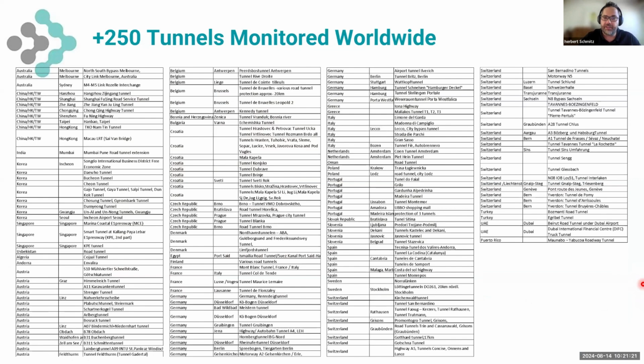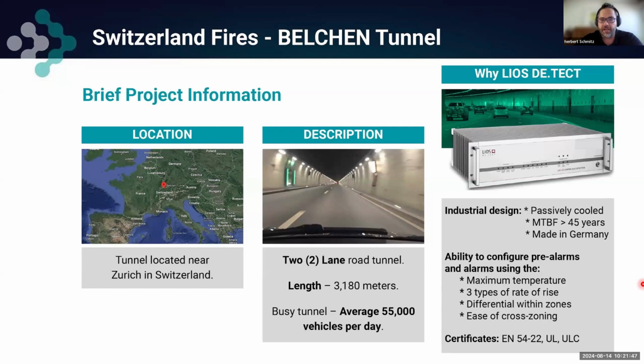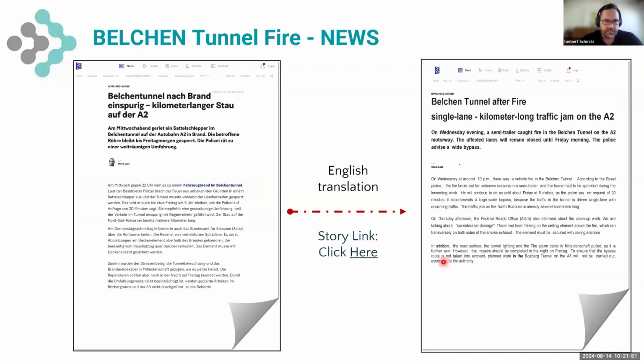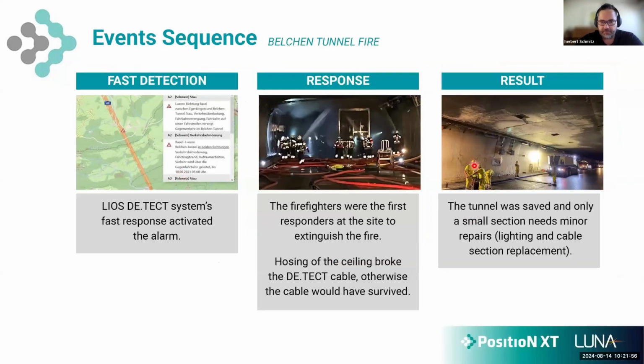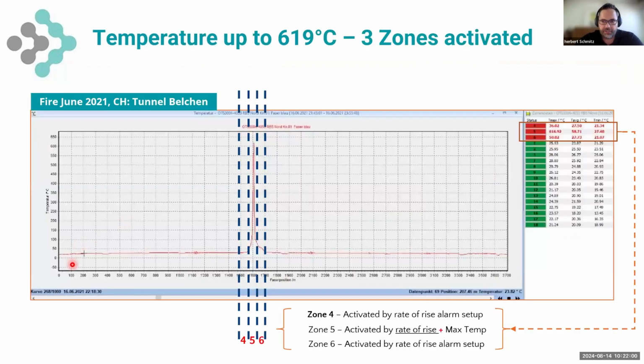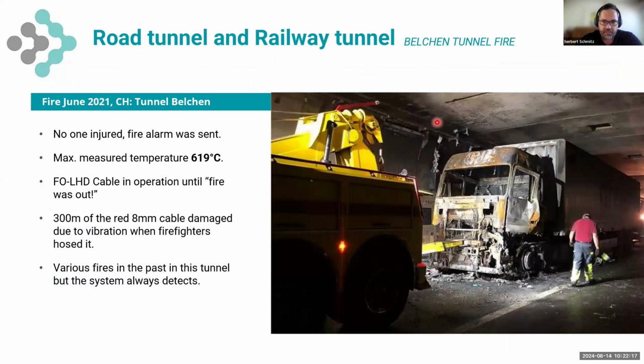But mines are just tunnels. And the reality is that this technology has been used successfully within other industries and within the transport sector for decades already. We have done over 250 tunnels, being rail and motorway tunnels, throughout the world. And this technology has actually been proven quite successfully. I've got 2 examples here of 2 major fires within Europe, where this one in Switzerland had a major fire, and our system was installed within that tunnel. To give an idea, in this case we measured exactly the location of the fire. It went up to 619 degrees Celsius. We continually monitored the temperature throughout that fire event. You can see our sensor cable was directly within this fire, and it was still fully operational.